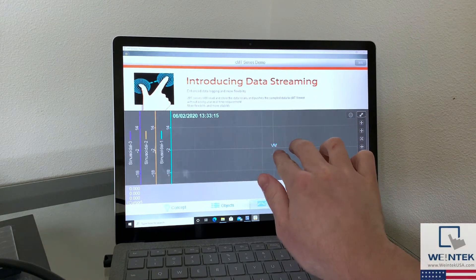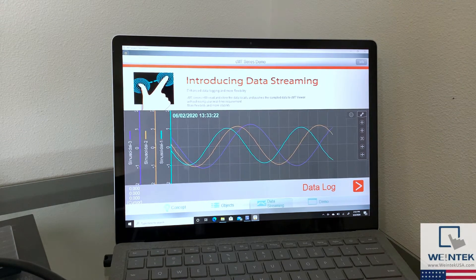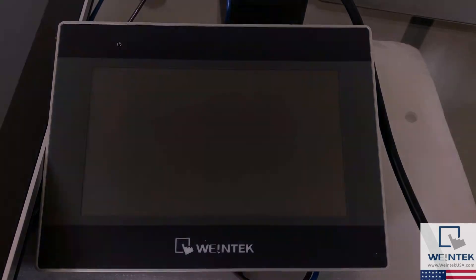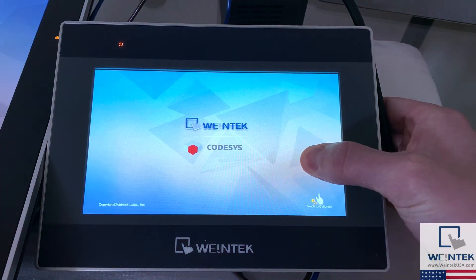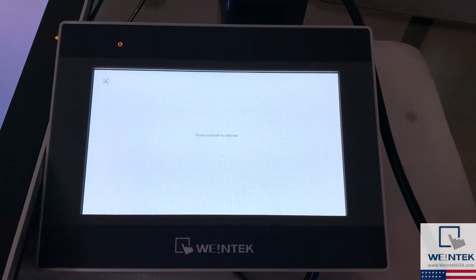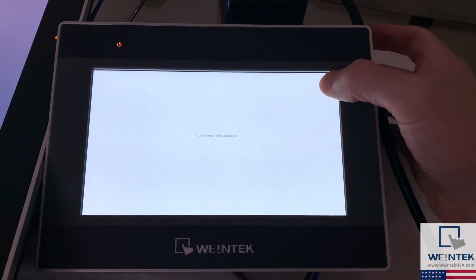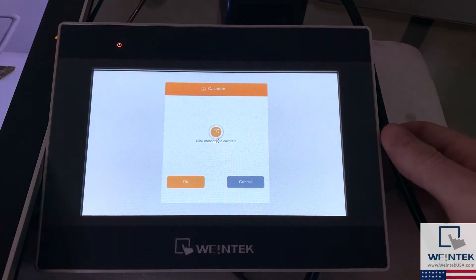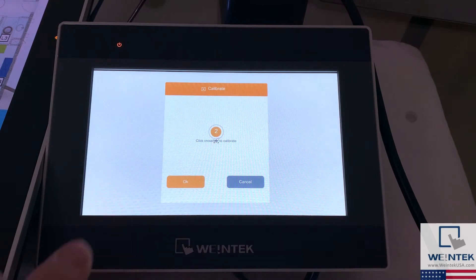The next topic I'd like to discuss is touch calibration. Although this won't be a feature you'll use all that often, I'd like to show you just how easy it is to perform. I'll begin by powering down my 3072. As I power on my device I'm going to place a finger on my touch display and hold it there for roughly two seconds, after which a new screen will display with a small square in the top left corner. I'm going to select the square and it will progress around each corner as I touch it. On our fifth calibration attempt it will move to the center where I'll select it for the last time. A menu will display stating 'click OK to calibrate' and I'll go ahead and click OK, and our HMI project will then boot.